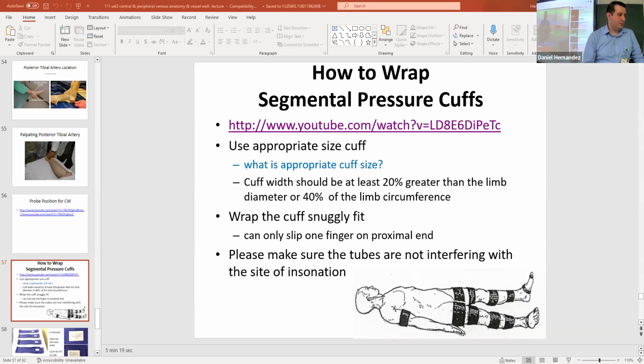Now, there's one other option for the thigh cuff, and that's in the 3-cuff method, using one large thigh cuff. This is a 17 or an 18 centimeter cuff. It's actually quite nicely designed in that it's conical in shape, so it fits and contours the thigh a little bit better than the straight 12 centimeter cuffs. You can see the conical shape here. And also this has 2 different Velcro straps, so it makes it a little bit easier to cinch this larger cuff down. So this would be the 3-cuff technique: 1 thigh cuff, 1 calf, and 1 ankle cuff.